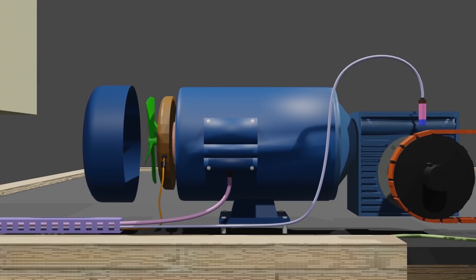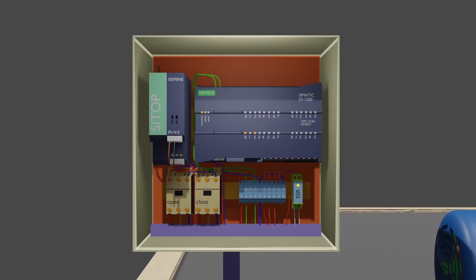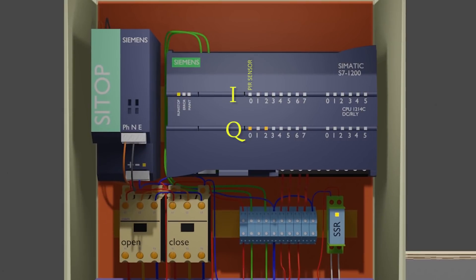Now let's see the PLC wiring. We have connected the PIR sensor at I0.0, the count sensor at I0.1, the brake coil at Q0.0, the door open contactor at Q0.1, and the door close contactor at Q0.2.